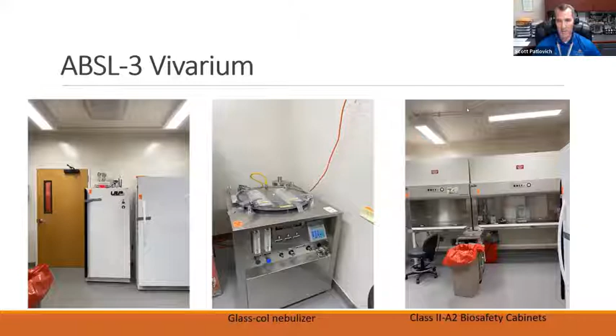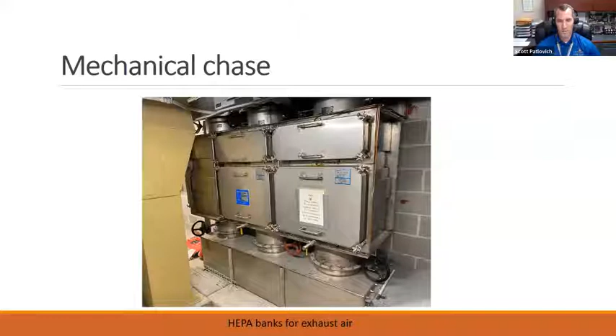Back in the mechanical chase, these are the HEPA filters. We've got a pre-filter and the actual HEPA filters themselves that all of the air exhausted out of that laboratory space goes through prior to exhaust out of the building, no recirculation whatsoever to any other part of the building to ensure single pass, 100% exhaust air. Here in Houston, it's hot and humid for a good part of the year. And so that costs a lot of money, but it's very, very important to do as part of the lab containment feature.